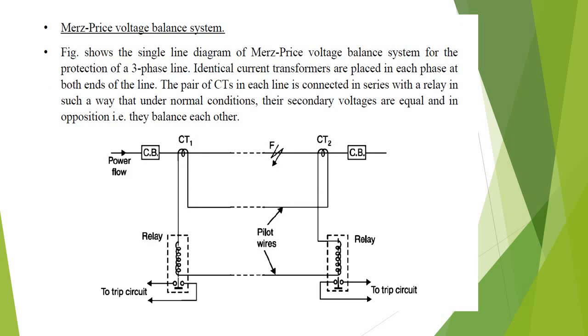Differential protection is a pilot wire protection. This is the single line diagram of the Merz-Price voltage balance system of protection of three-phase lines. Identical current transformers are placed in each phase at both ends of the line. Each pair of CTs is connected in series with the relay. Under normal operating conditions, the secondary voltages are equal and in opposition, balancing each other.